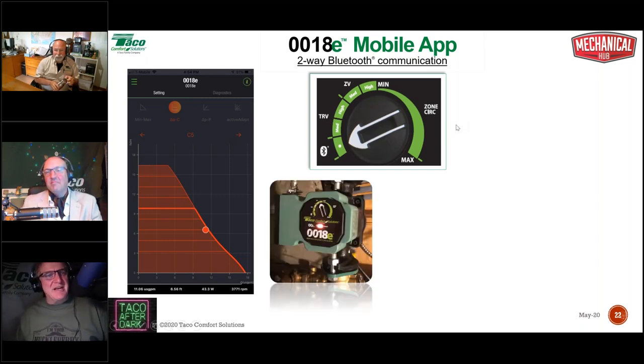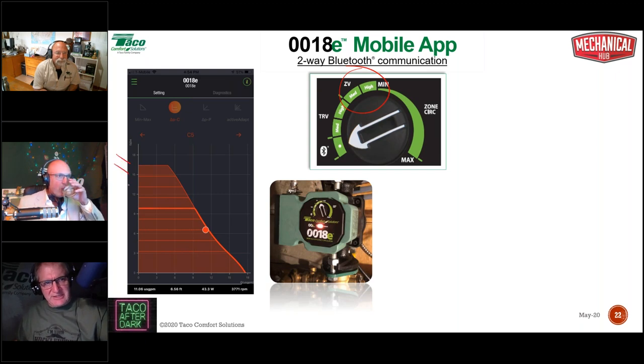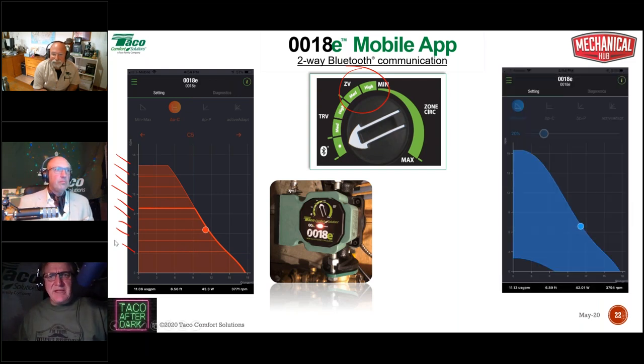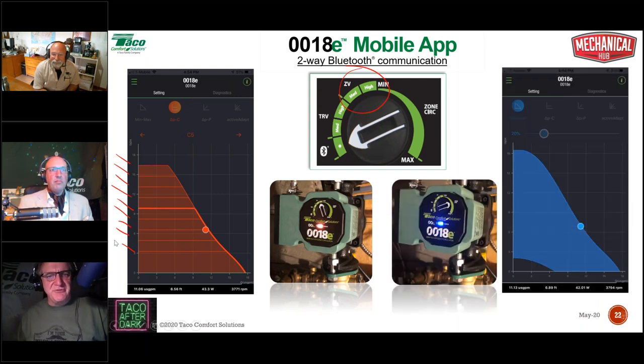Then we have the constant pressure settings. I was just getting ahead of myself. Instead of two constant pressure settings like we would have on the dial for zone valves, we actually now have nine to choose from. And then we have that adjustable fixed speed. That adjustable fixed speed can be adjusted by using this slider. You simply put your finger on that slider and you can move it up and down and you can change the speed of the pump.